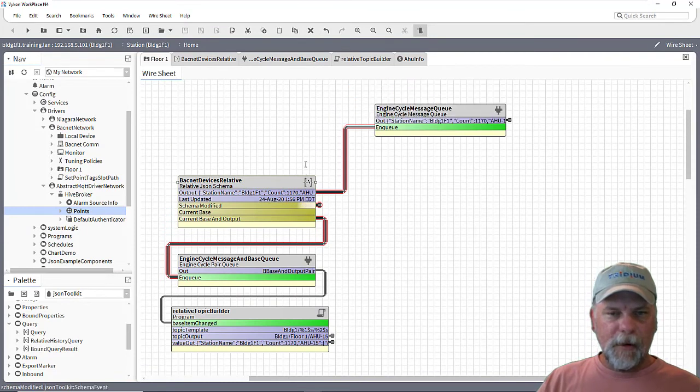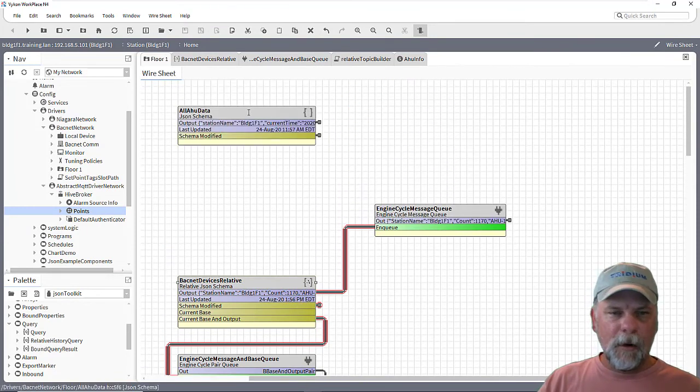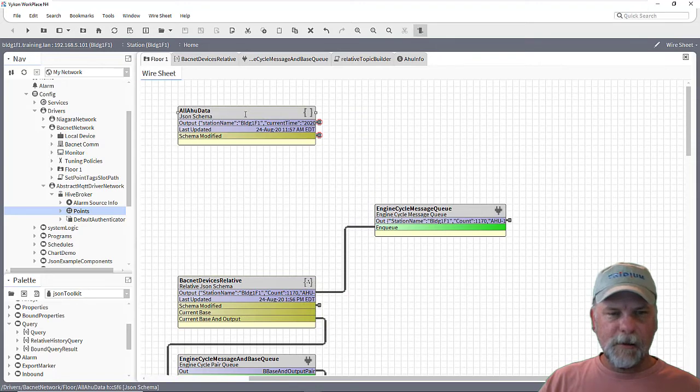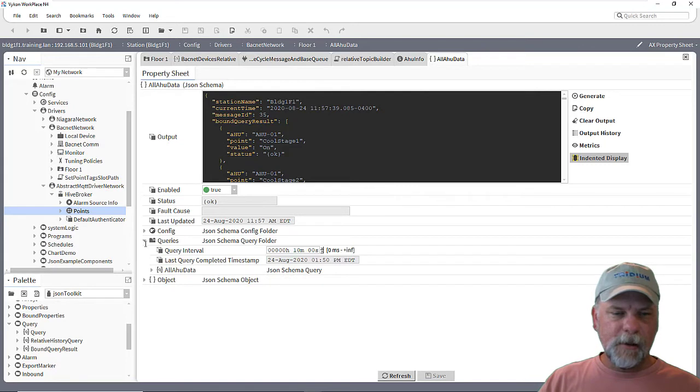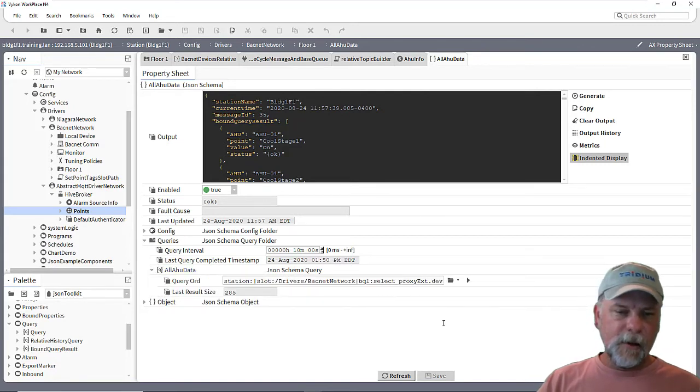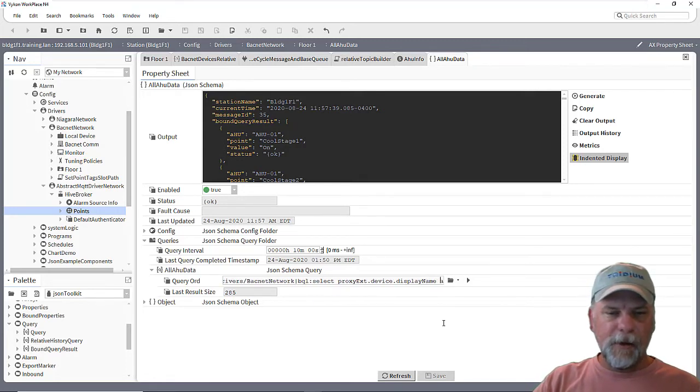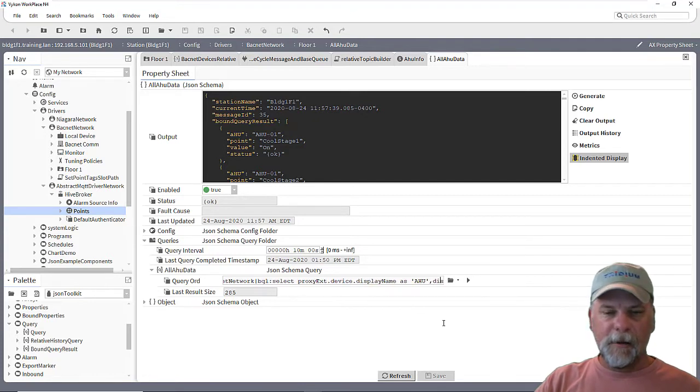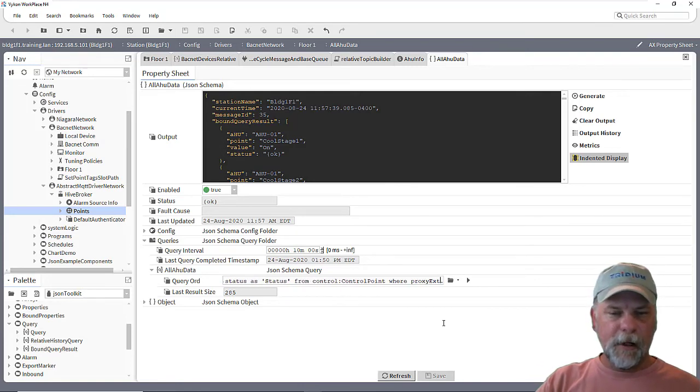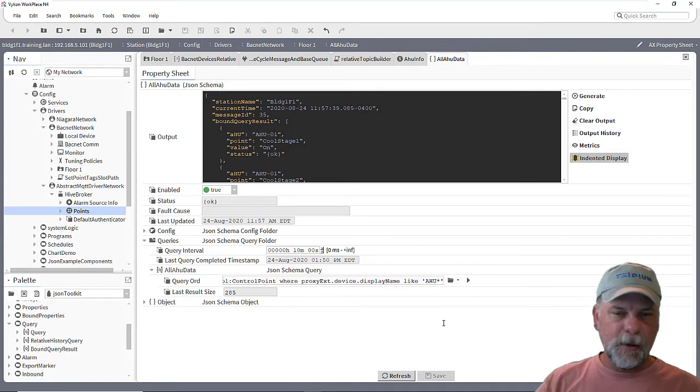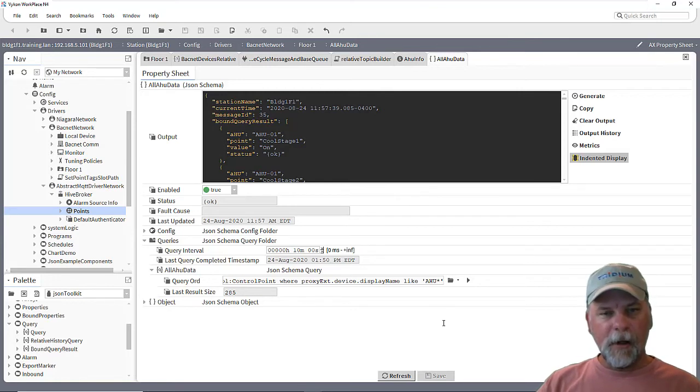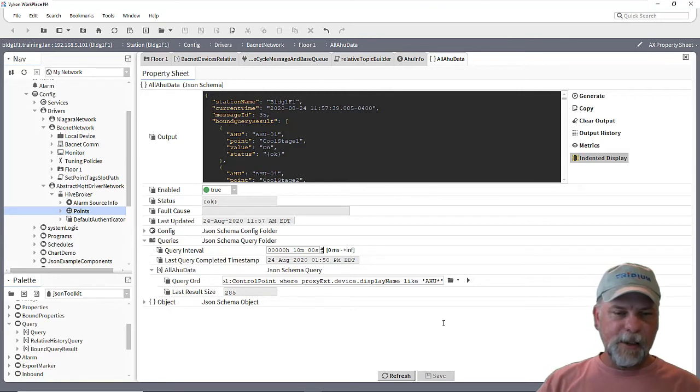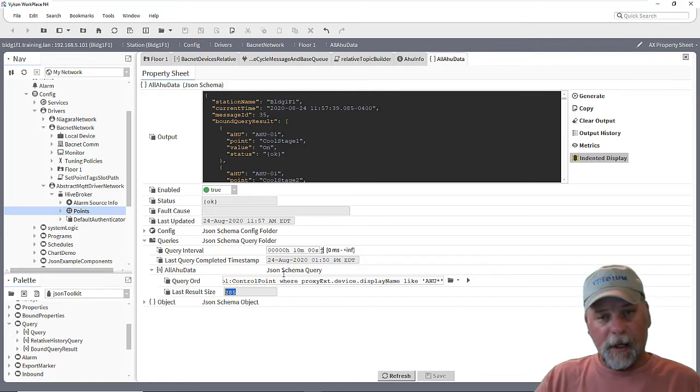So talked about a few different things, but just kind of in summary, one was to use a single JSON schema and that JSON schema was using a query that was querying for all the air handler data. So it's basically looking at the BACnet network and then doing a BQL query to display the device name, the display name of the point, the value of the point and the status. And that was the extent of the query was from control points. And we were using a predicate to limit it to just proxy points that were under air handler devices. So with one schema, we were able to export basically information from 285 control points under 15 devices to a single string published point, which might be what your client's looking for.